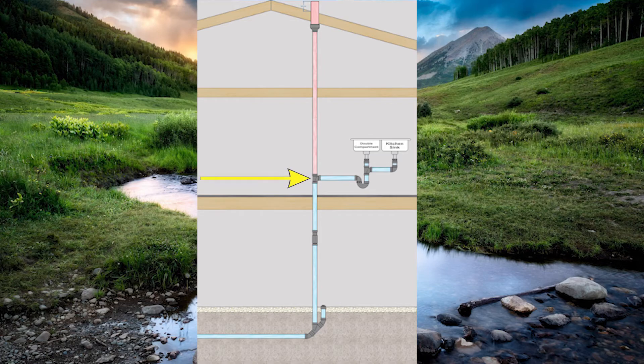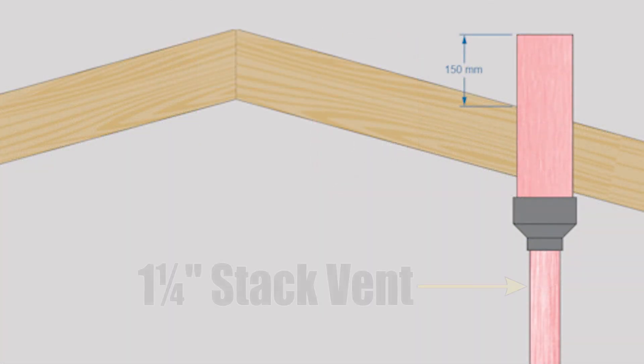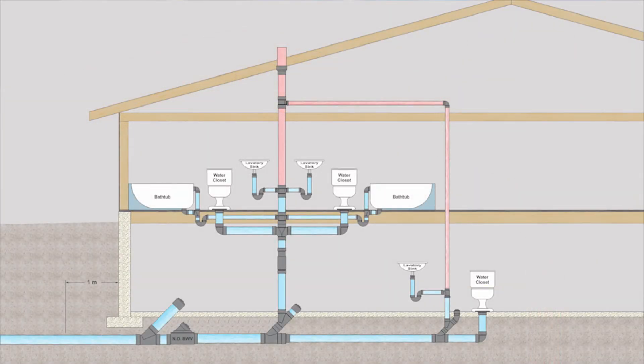Say for example that kitchen sink went straight up with the stack vent right through the roof. I would need to increase that one and a quarter inch pipe to three inch before passing the roof to protect from frost closure.